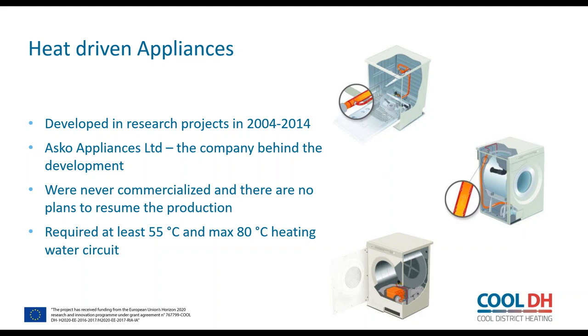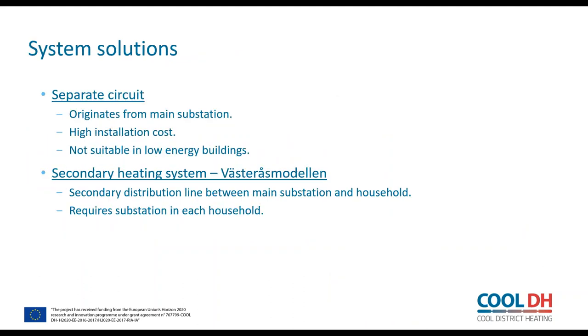So this was a slightly discouraging discovery, but it was decided to evaluate the appliances and how they would have performed at the Swedish and Danish test sites. The only prerequisites given by Asko were that the inlet temperature had to be at least 55 degrees to achieve any worthwhile electricity savings, but not higher than 80 degrees Celsius, that is, to not damage the hoses.